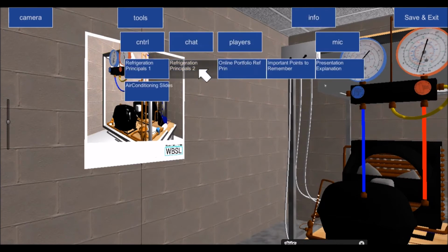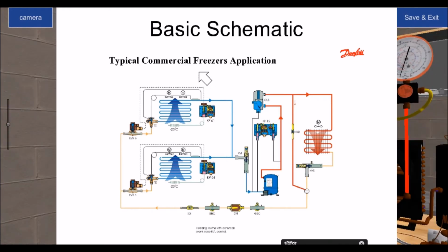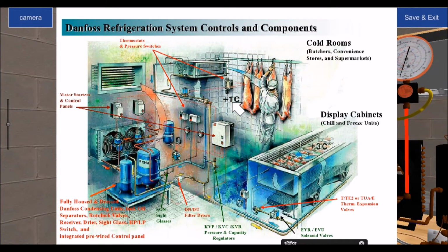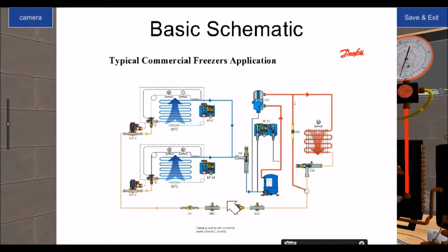if I was to go back up, it can also represent the evaporator pressure regulator. So this here is representing an evaporator pressure regulator, and the crankcase pressure regulator is closer to the suction side of the actual crankcase of the compressor. The two I will explain. This one, because of the nature of the way it is, is an actual crankcase pressure regulator, and I explained the function of that. Compressor.